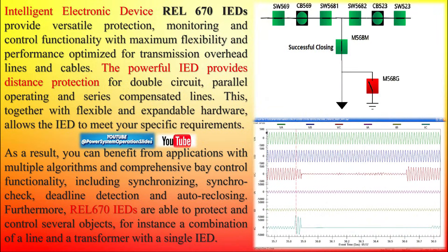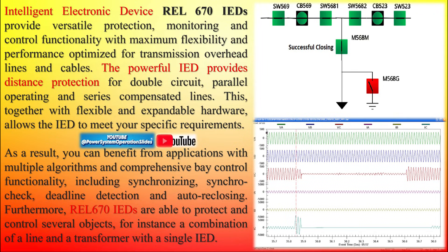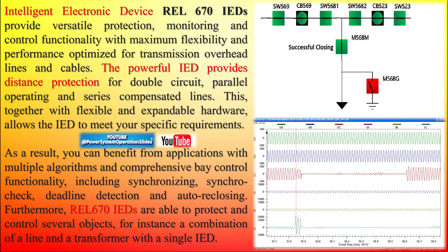Switch-on-to-fault (SOTF) is an important protection feature in modern intelligent electronic devices (IEDs) such as the REL670 Line Distance Protection Relay. It is particularly relevant when a circuit breaker (CB) is manually or automatically closed onto a line that is already faulted. The purpose of the SOTF function is to provide very fast fault detection and tripping to minimize equipment damage and ensure safety.